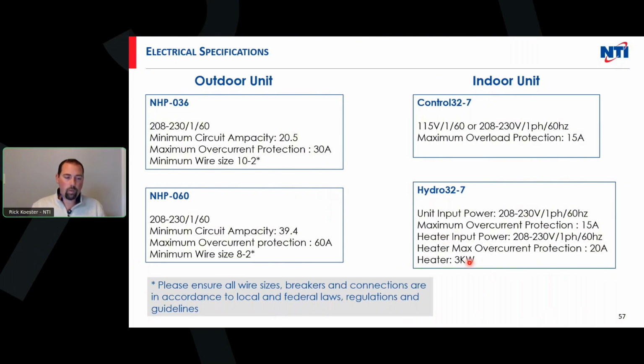So we are all about ratings. The 3 kW is rated at 230 volts. So if they were bringing in 208, then you would have slightly less performance. I forget what the number was. If it was 3 kW on 230, it's something like 2.7 something kW if you did 208. So there is a little bit of a derating there.